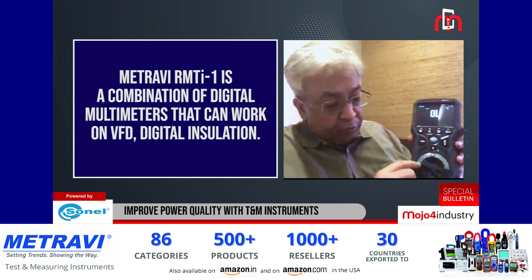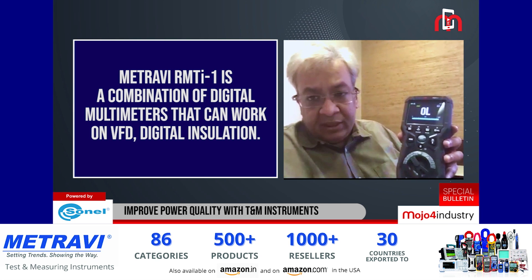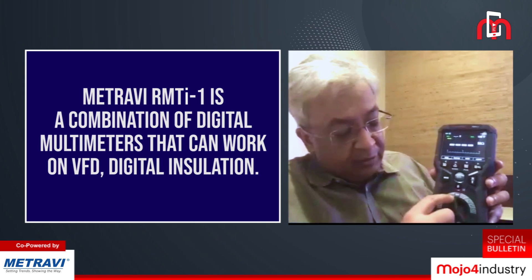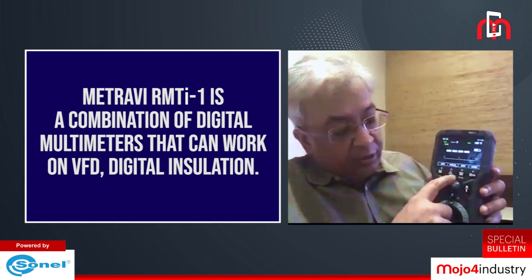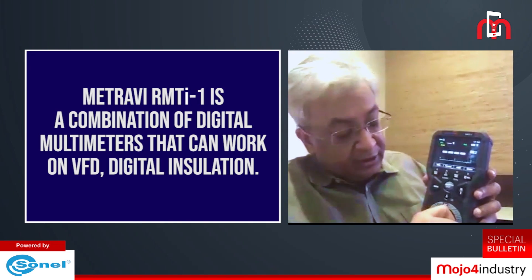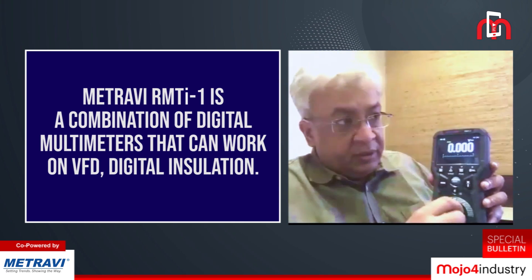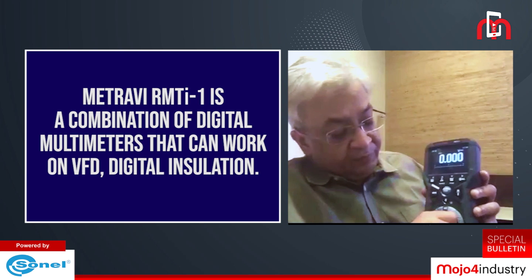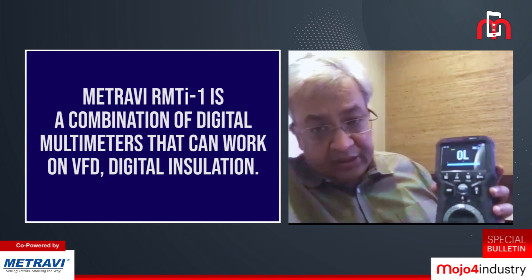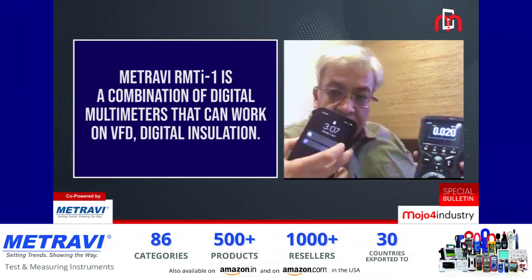You can use a contact-type probe to measure temperatures at various points. The low resistance measurement for winding resistances tells you if winding resistance is within range — because if winding resistance is high, current consumption increases and the motor overheats. This instrument measures insulation resistance from 125 V to 1000 V, up to 5000 MΩ, with polarization index (PI) and DAR measurement, suitable for both transformers and motor or generator testing. It can also function as a multimeter measuring AC and DC voltage, has a low-pass filter to remove high-frequency noise, DC voltage measurement with frequency, and simple resistance measurement. All readings can be transferred to your mobile phone via Bluetooth.